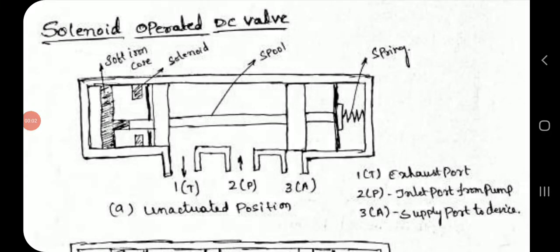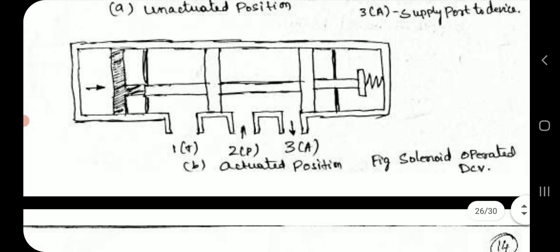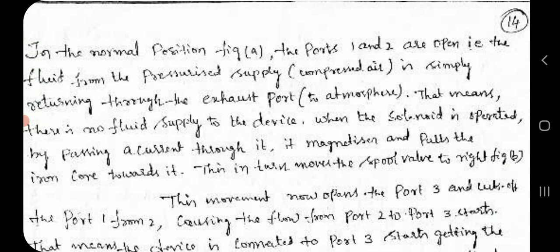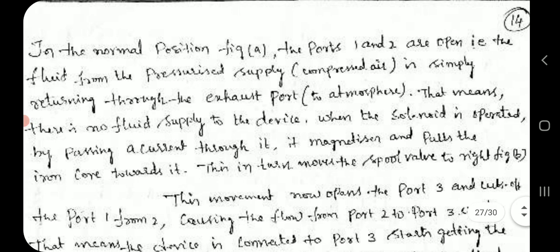Solenoid Operated Direction Control Valve. In the normal position, Figure A, ports 1 and 2 are open — that is, the fluid from the pressurized supply (compressed air) is simply returning through the exhaust port to atmosphere. This means there is no fluid supply to the device.